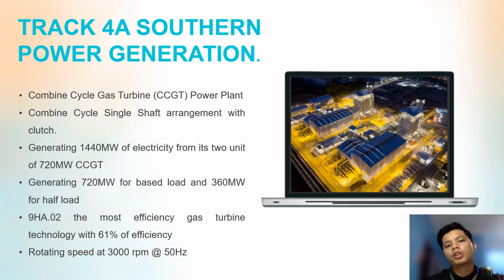The Track 4A Southern Power Generation is a combined cycle gas power plant. It combines the gas turbine with the steam turbine. It is a single shaft arrangement with clutch. From one unit, it will generate about 720 megawatt for its base load and 360 megawatt for half load. This power plant uses the 9HA.02, the most world efficiency gas turbine technology with 61% efficiency. This gas turbine will rotate at speed 3000 rpm with 50 Hz of frequency.